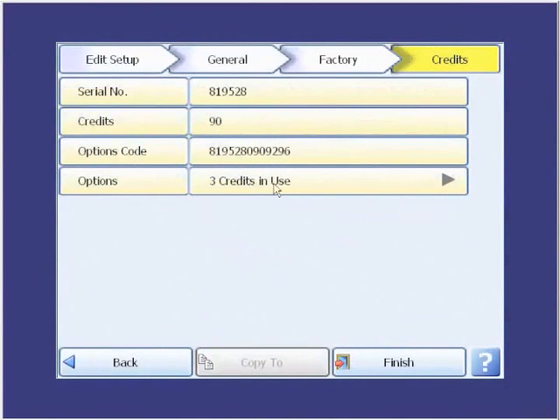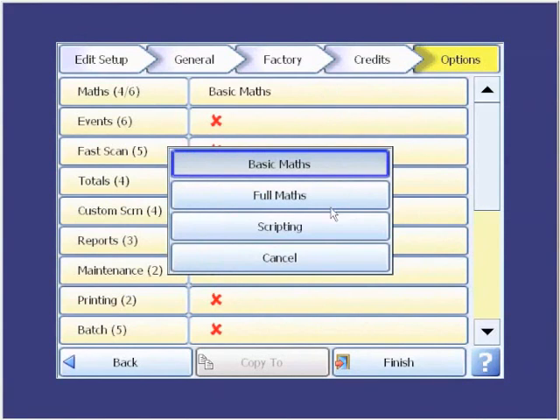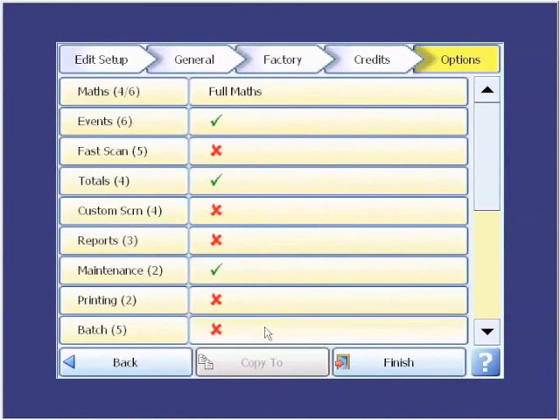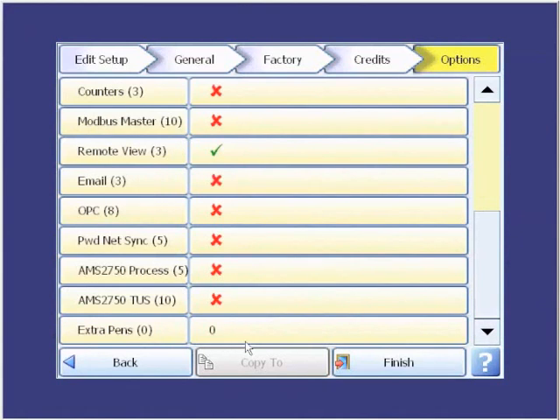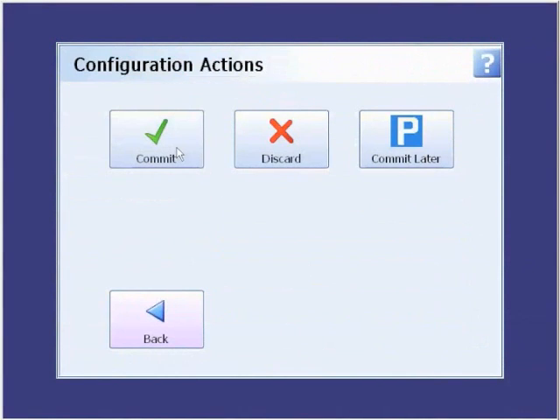Down here, we have the option — it tells us how many credits are available and then how many are in use. We click on the bottom one for the ones in use. We want to change basic math to full math, so we make the selection. We want to enable events, which allow us to do cause-effect operations with the recorder. We do not need fast scan. We need to enable totals for some flow totals, enable maintenance which is a diagnostic function, and enable batch because that's what the recorder is going to be used for. There's a vertical scroll bar on the side — scrolling down, remote view has already been enabled. Going all the way to the bottom, we get extra pens. We need four extra pens for this application, so I come in, put in four extra pens, and enable that. Then we finish and commit the changes.